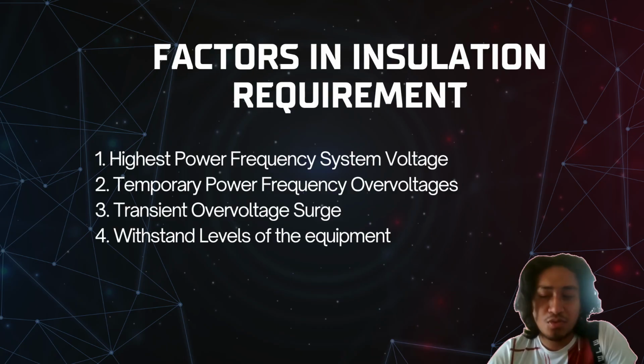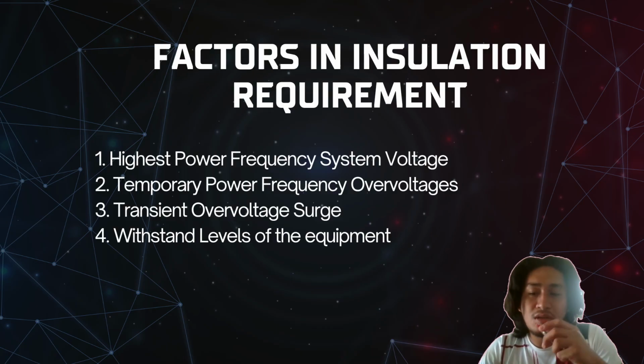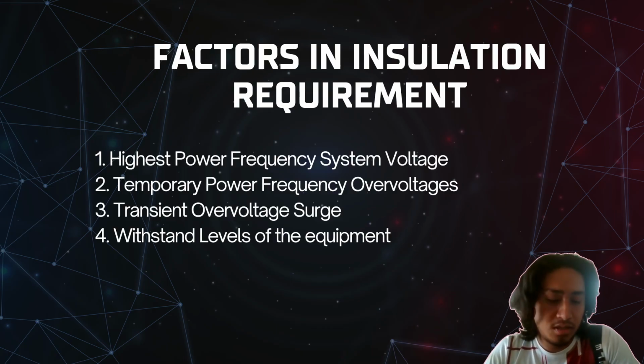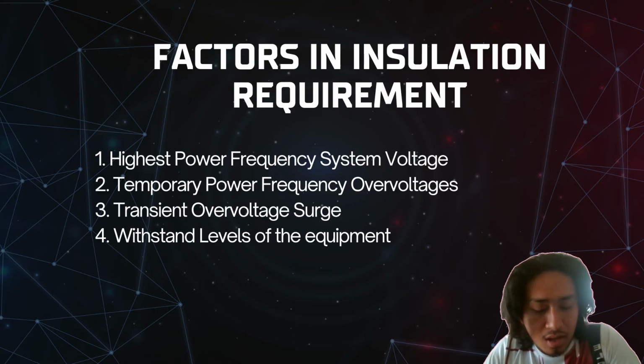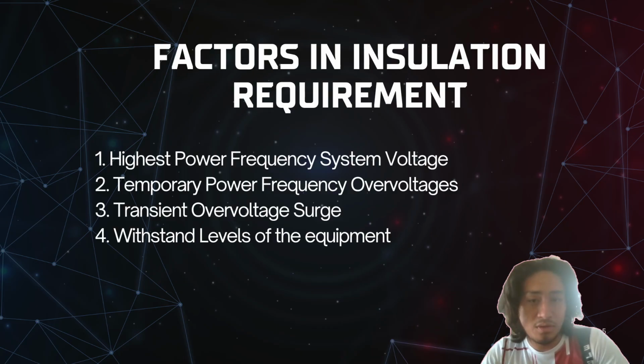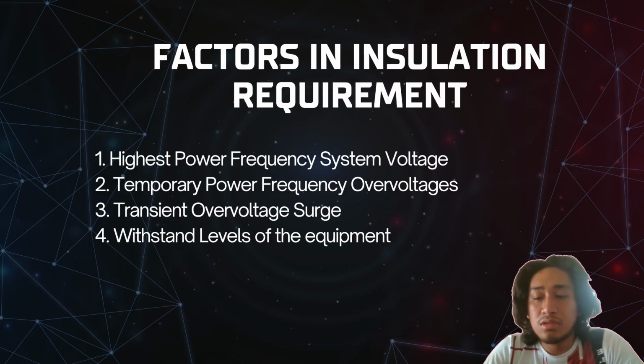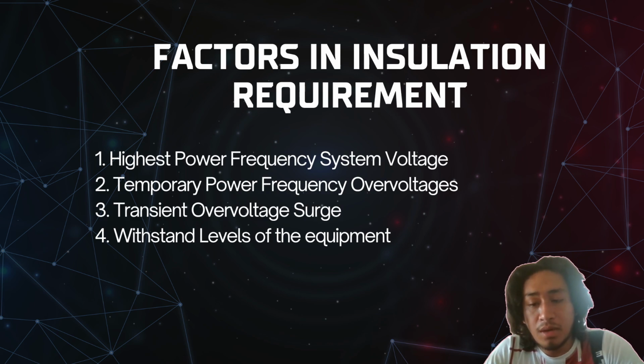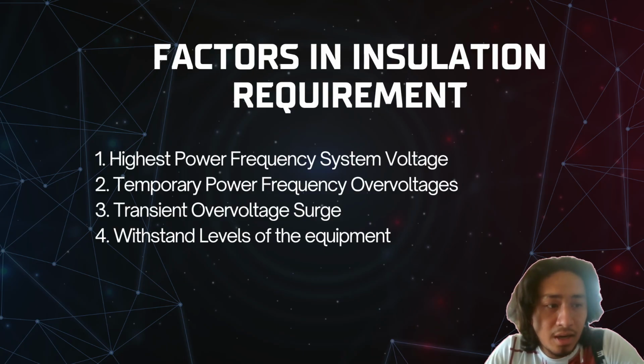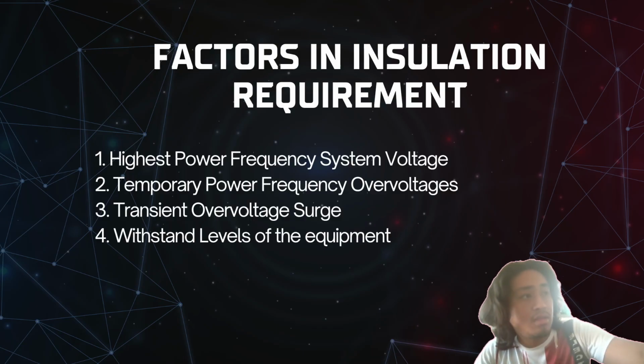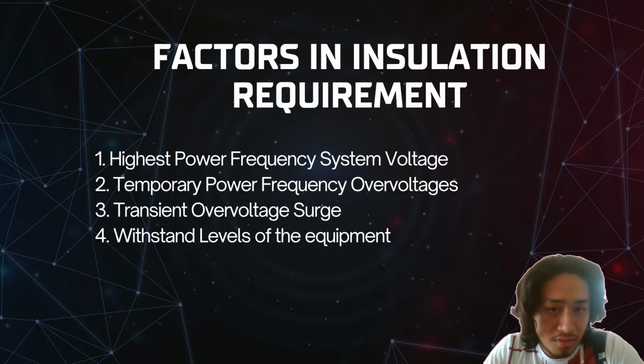Let's proceed to the factors in insulation requirements in our system, since this is very crucial when coordinating your insulation with respect to your voltages in different aspects. So insulation requirements in a power system ensure reliability by preventing electrical breakdown. Electrical breakdown is a phenomenon where the electric strength of your insulator has been exceeded by the voltage.